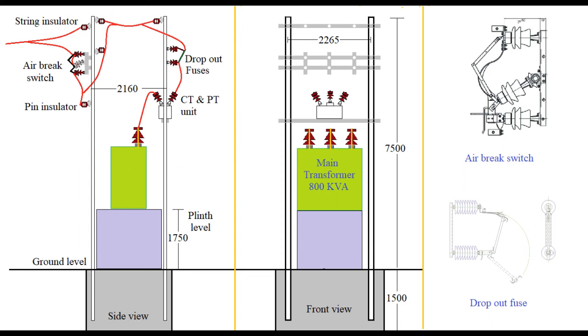Conductors for any one of the phases are seen to travel between the outer incoming feeders, then the air break switch, then the pin insulator at bottom, and finally a jumper is connected from the lower portion of the conductor to the inner overhead lines between the 2 pairs of poles. Jumpers are short length conductors that connect to other conductors using steel connectors.